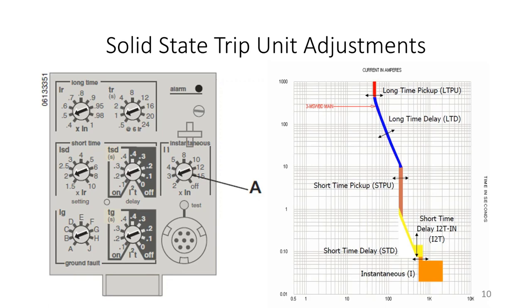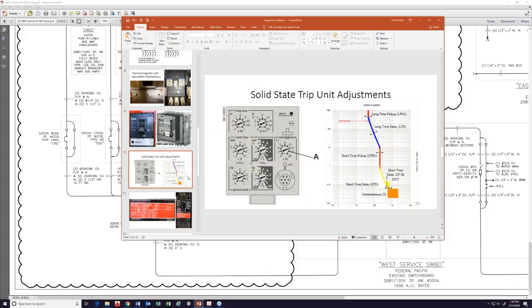Now, it is amazing, especially now with some of them having the maintenance duty, that I can have a very nice setting of selectivity, but yet an electrician can walk into the job, press that button, and have that trip unit change to the lowest and most sensitive setting so the arc flash goes down. And it appears that I've achieved both worlds, but that's not necessarily true. This is going to require the electrician to remember, before he goes home, to turn off the maintenance duty. And if he doesn't, then it's not a good day. And there's other issues with it I'm not going to bother going into. But again, there are different options, where solid state is not always the answer.